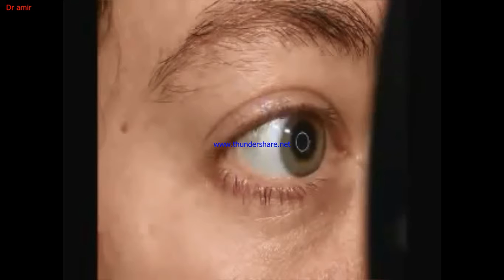Looking through the eyepiece, you will see the target mires. Note, the target mires may be blurred. If the target mires are blurred, turn the focusing knob to clear the image. The black plus sign should be in the center of the bottom right-hand circle. This is also known as our focusing circle. Turn the elevation knob if the plus sign is not in the center.